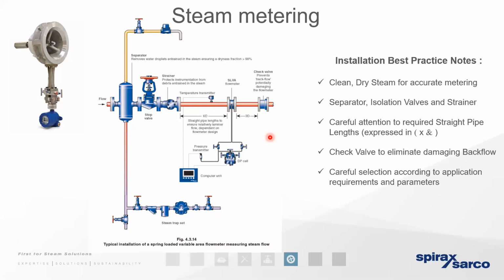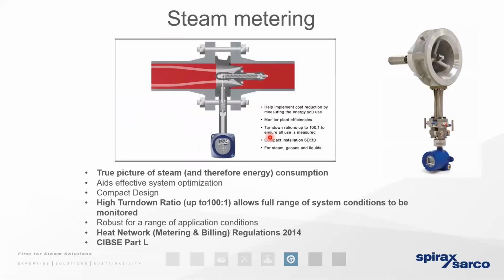So quite often we'll go to a site that's using steam. We'll ask them if they're metering the steam. They'll say, yes, we're metering steam, but we'll find out for whatever reason, either the meter isn't operating accurately for reasons we've already mentioned, or that it's been proved to be faulty because it hasn't been installed correctly. So we know the value of metering steam.